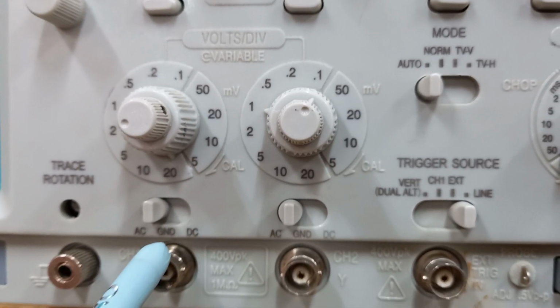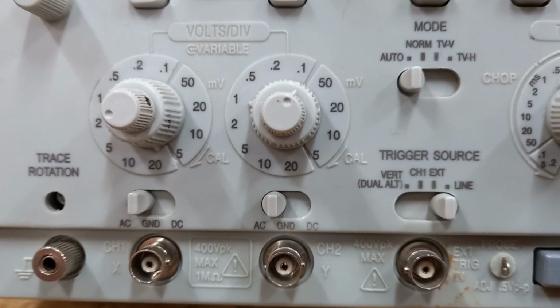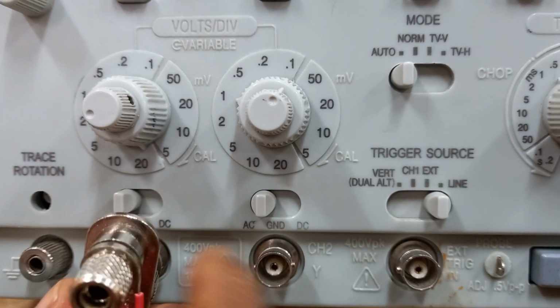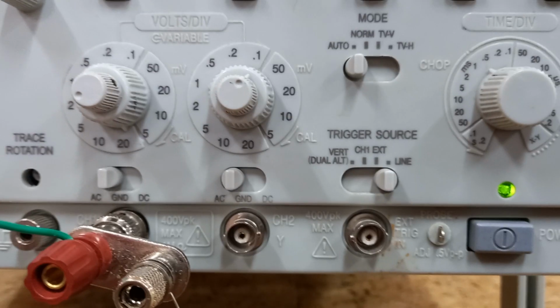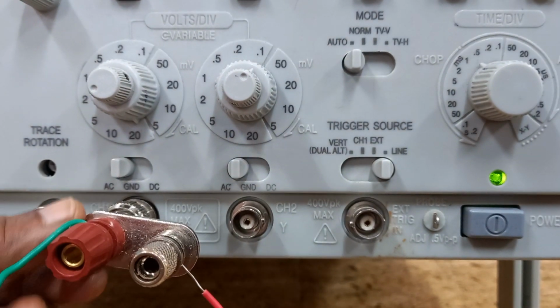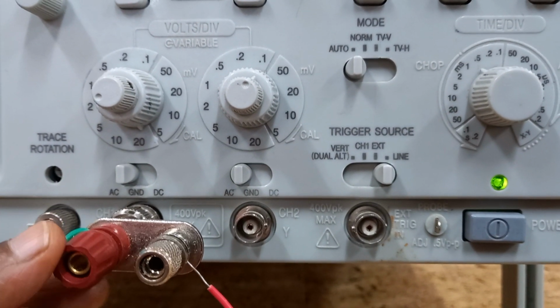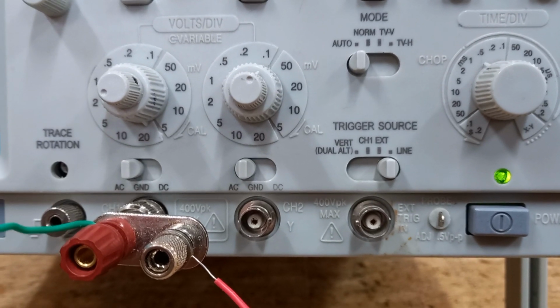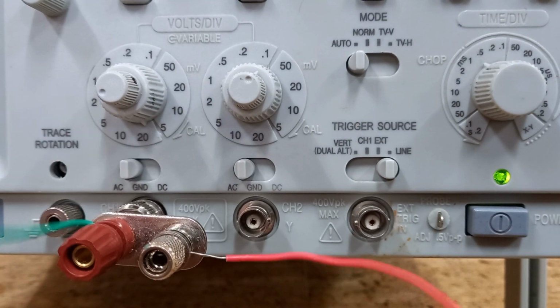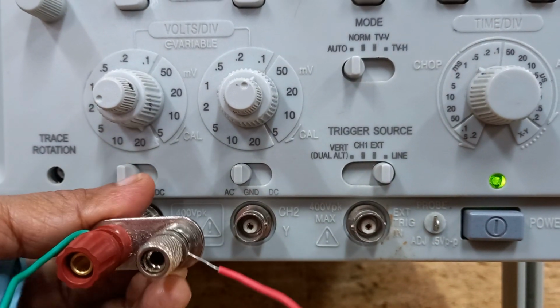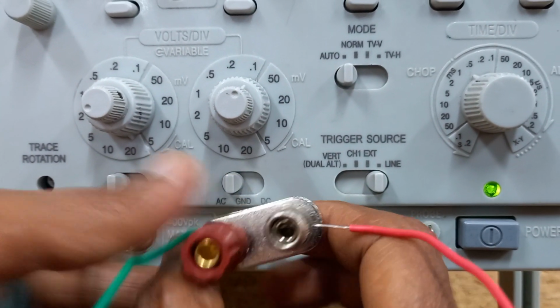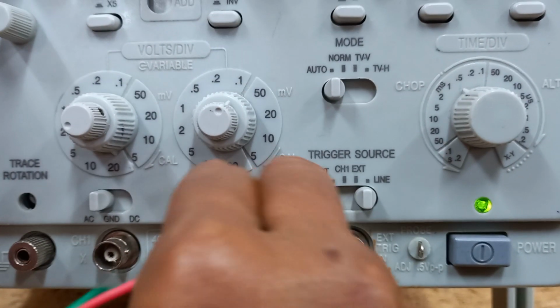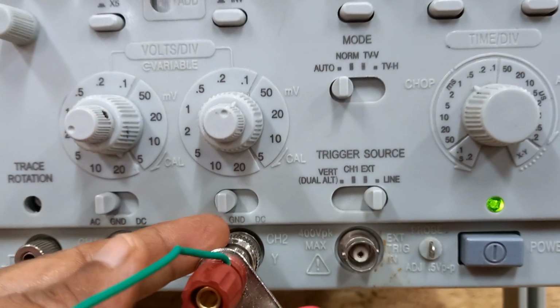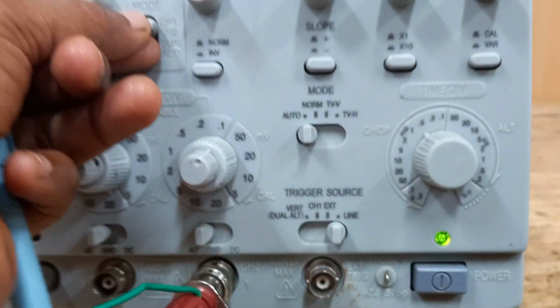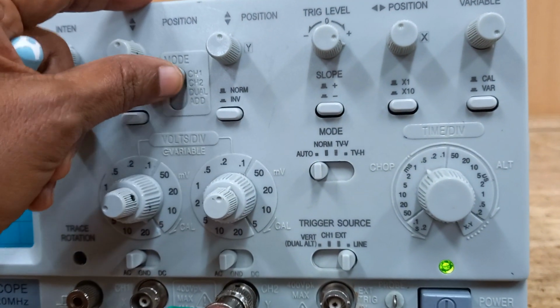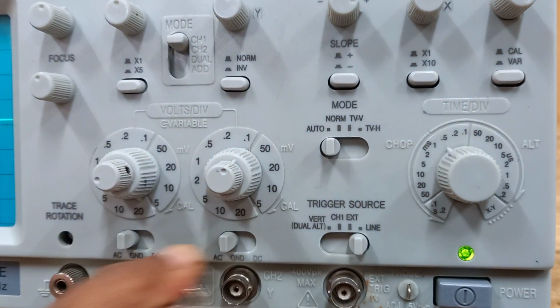So this is the channel 1 point where you will connect your CRO probe. Either you can connect a T connector or a CRO probe. Today I am using a T connector, which has a positive and a ground terminal. In the same way, for channel 2 also, you can connect the CRO probe or the T connector. If you are using channel 2, you have to select the position, that is channel 2. If you are using channel 1, connect your probe to channel 1.